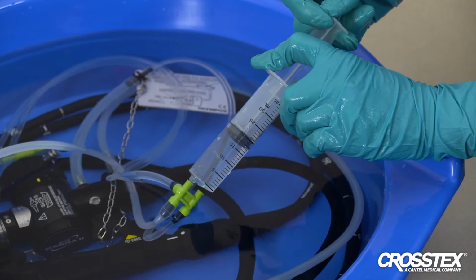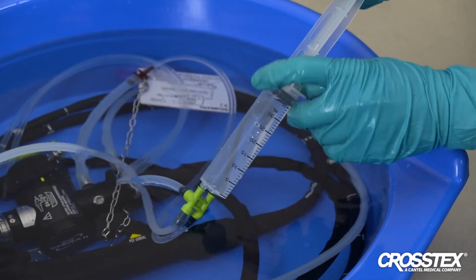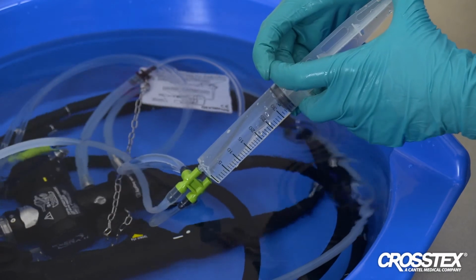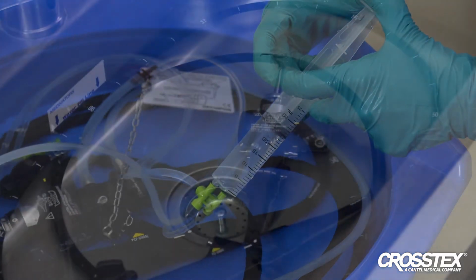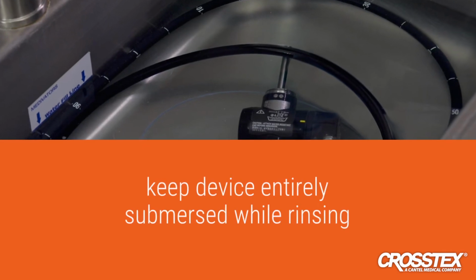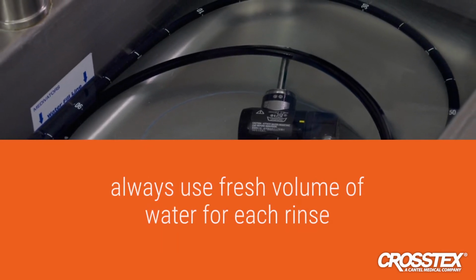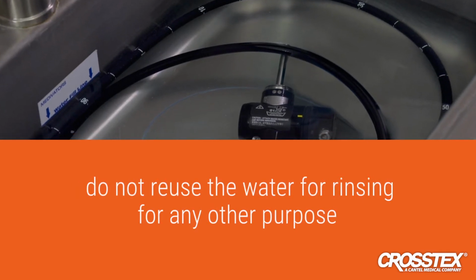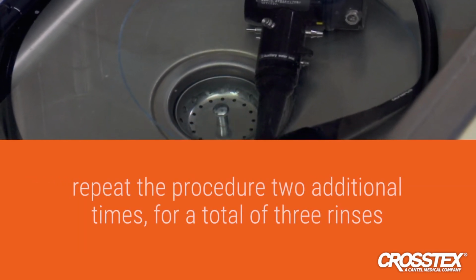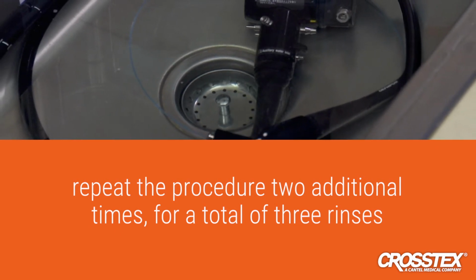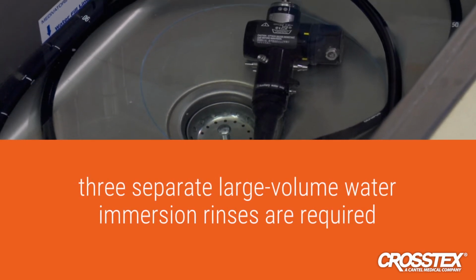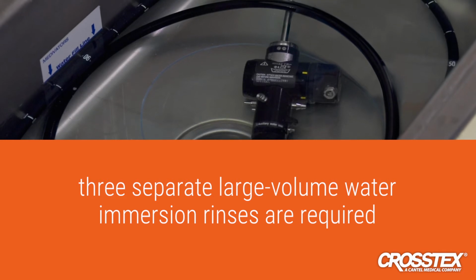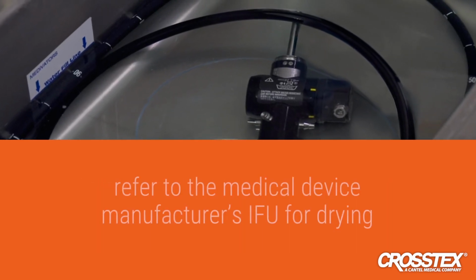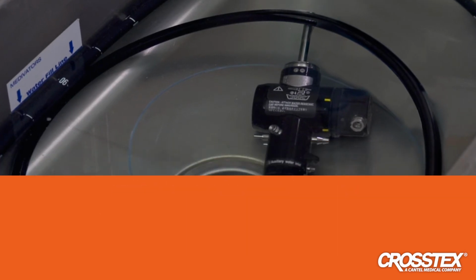Remove the device from the solution and rinse thoroughly according to the device manufacturer's rinsing instructions. In the absence of the device manufacturer's rinsing instructions, thoroughly rinse by immersing in a large volume of water. Keep the device entirely submerged while rinsing. Always use fresh volumes of water for each rinse. Do not reuse the water for rinsing for any other purpose. Repeat the procedure 2 additional times for a total of 3 rinses with large volumes of fresh water to remove any residue. 3 separate large volume water immersion rinses are required unless otherwise specified by device manufacturer's instructions. Refer to the medical device manufacturer's IFU for drying.